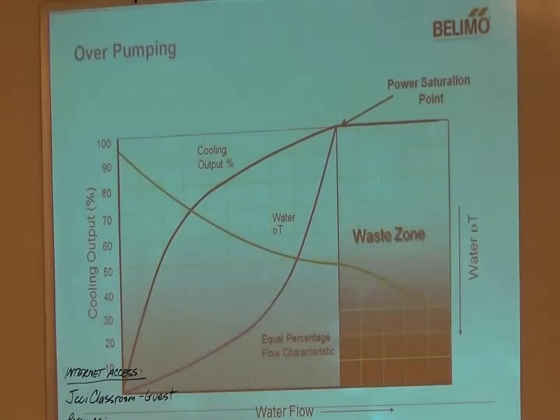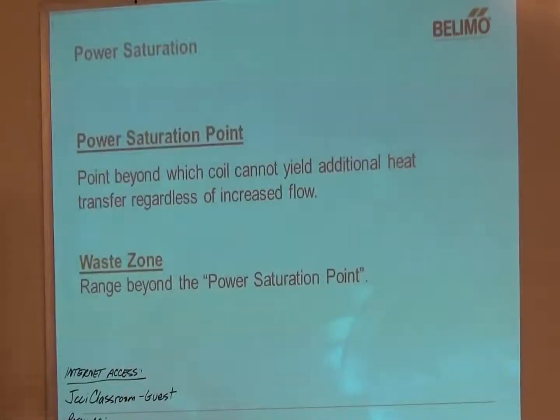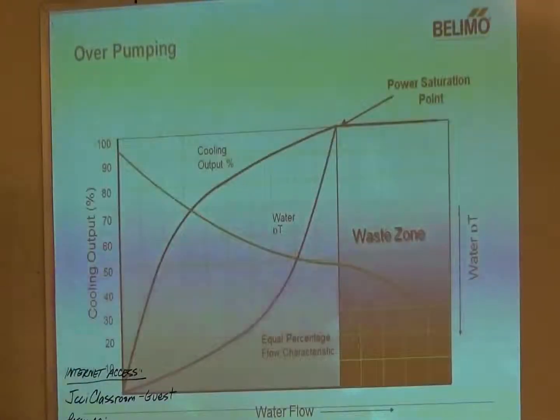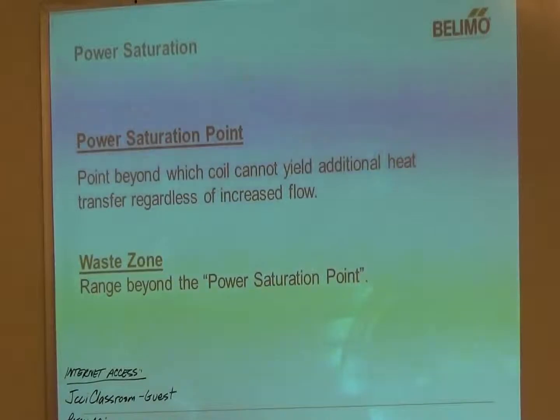Well, it's going to create a waste zone, because what you end up with is your power saturation point is right here. The power saturation point is the point where you've basically maxed out your coil. So beyond that point, any additional flow through the coil, you're not going to achieve any additional output capacity, or very little. So that's why we call it the waste zone. Power saturation point, our definition: the point beyond which the coil cannot yield additional heat transfer regardless of increased flow. And then the waste zone, obviously from this graph, is the range beyond the power saturation point.